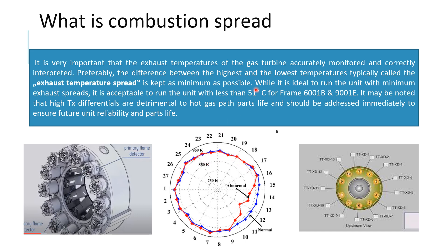The allowable spread should be around 50 to 70 degrees Celsius — I have seen in 6B machines it can be up to 69 degrees. A spread in that range is considered normal behavior. Spread is calculated by taking the maximum exhaust temperature and subtracting the minimum. For example, if the maximum temperature is 700°C and the minimum is 650°C, the difference is 50°C — that is the spread.